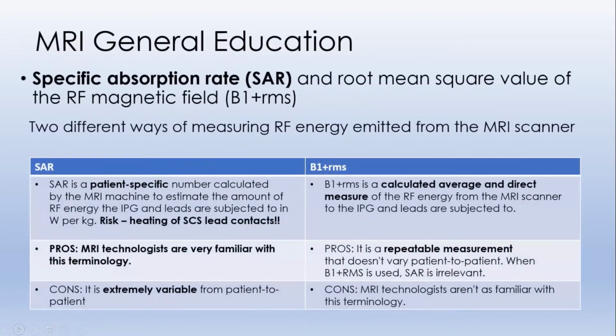Just a short note on how we measure the RF energy emitted from the MRI scanner. It's mainly by measuring the specific absorption rate, abbreviated SAR. This is a patient-specific number calculated by the MRI machine, which estimates the amount of radio frequency energy that the patient, but also the IPG and the leads, are subjected to, in watts per kilogram. Why is this important? Because if this number is too high, there's a risk of heating of the SCS lead contacts, which might cause an injury, primarily to the spinal cord. The pro of SAR, which is mainly used today, is that most MRI technologists are very familiar with it. The con is that it's extremely variable from patient to patient, and that's why people are now switching to root mean square values, which are much more reliable.